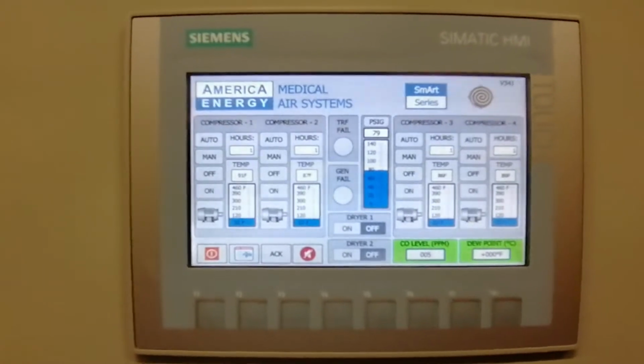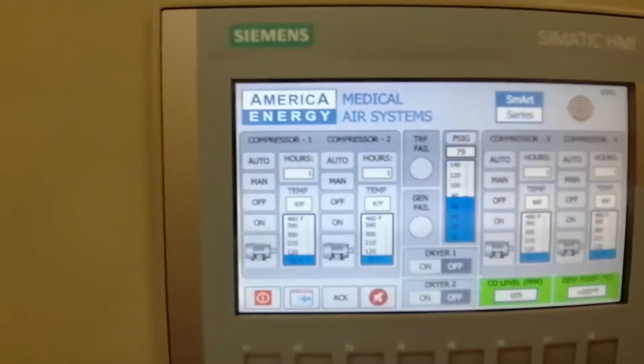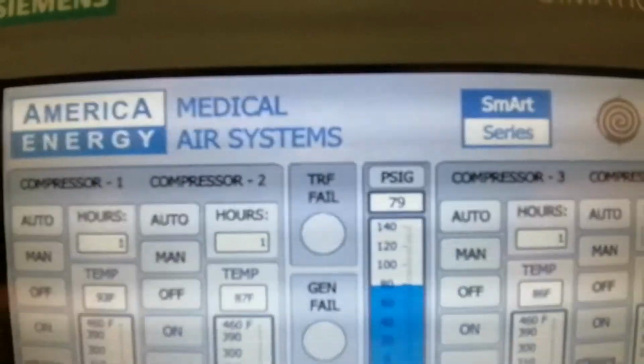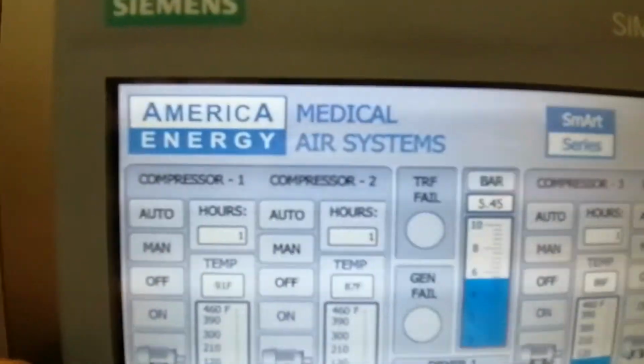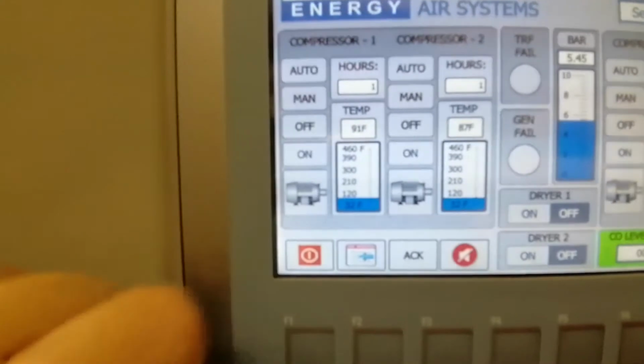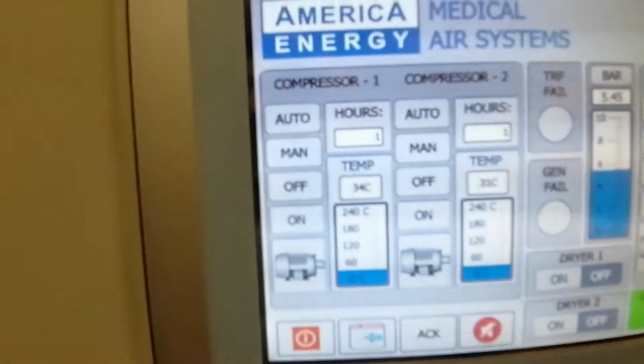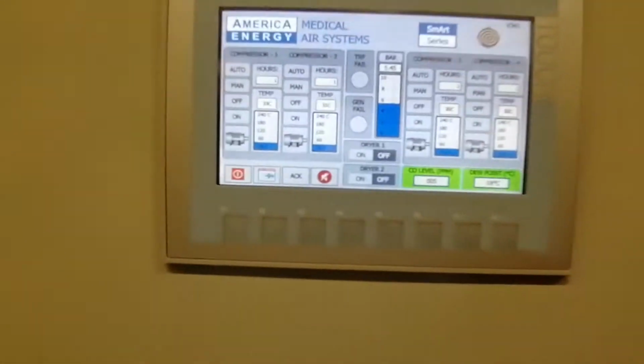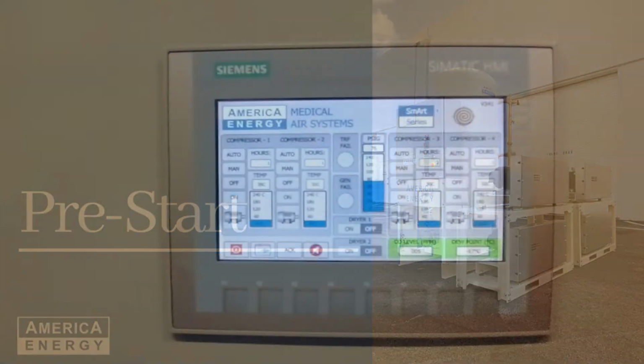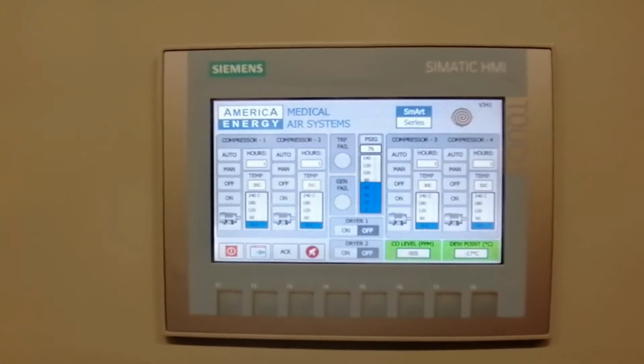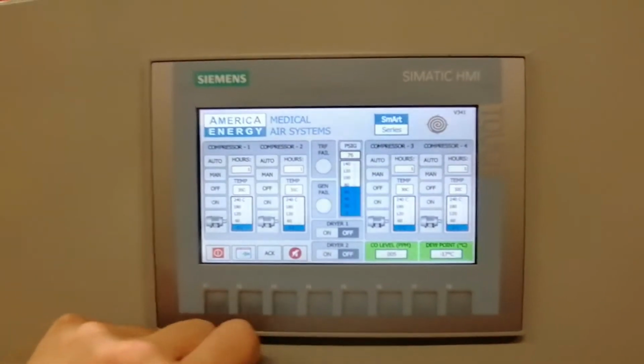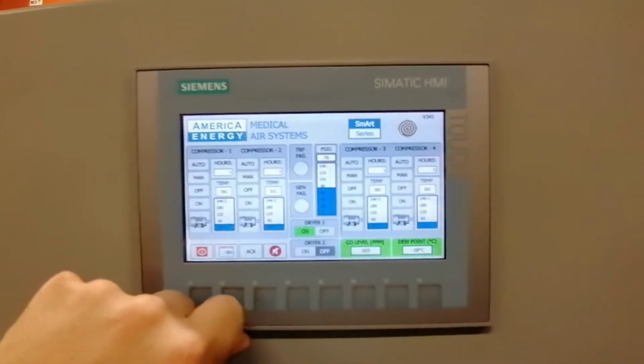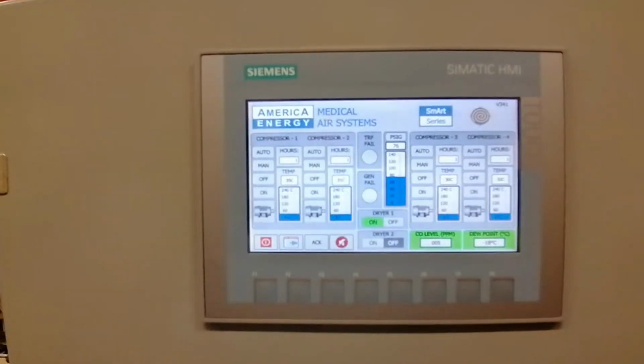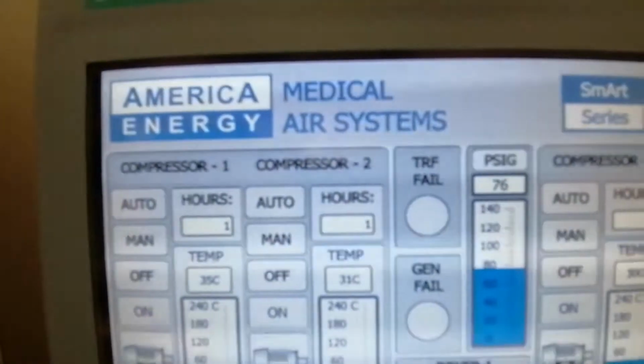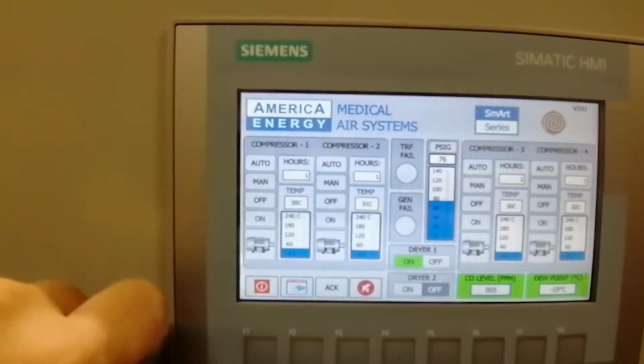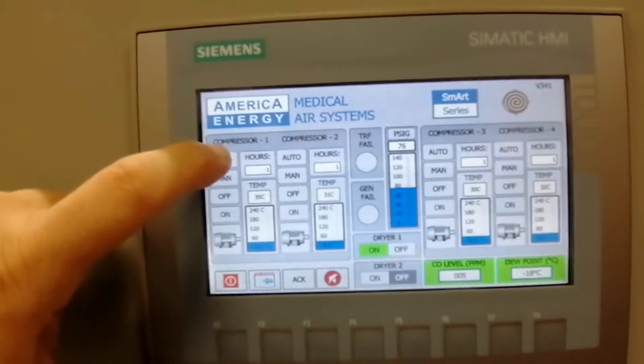In the HMI, you can change the unit for each parameter. For example, for pressure, you can see it in PSI, or by pushing the value it is shown in bar. Also the temperature in Fahrenheit, or by pressing the value it is changed to centigrade. After checking the rotation for each compressor in the system, select the dryer to operate, and then you are ready to start up the system. If the pressure is below 80 psi and you select compressor 1 in auto mode, it will start.